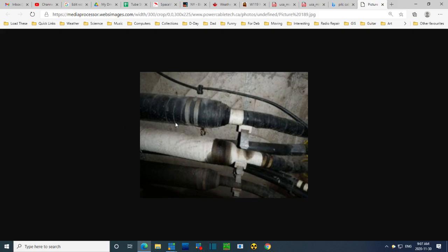So these cables have oil in them, but it's not exactly free oil. There's a little bit of excess oil, but it's not like oil is flowing up and down them. The paper has been impregnated with oil. So what they do is, after they put the paper on the cable, they take the paper-insulated copper conductors and stick them in a huge tank, a big reel of this stuff. I've seen the tank. Huge tank. Seal the top and then evacuate the tank. So they pull a vacuum inside this huge tank with the cable inside. It pulls the air out of the paper fibers, which are like little tubes.